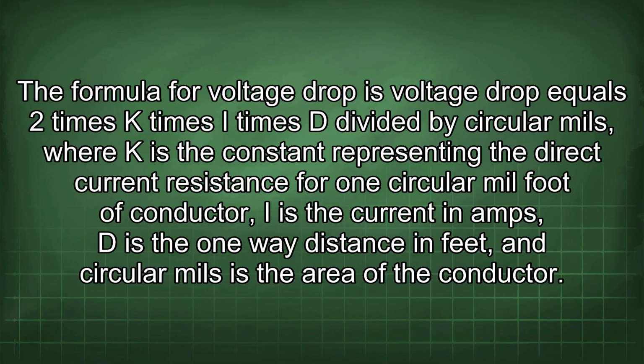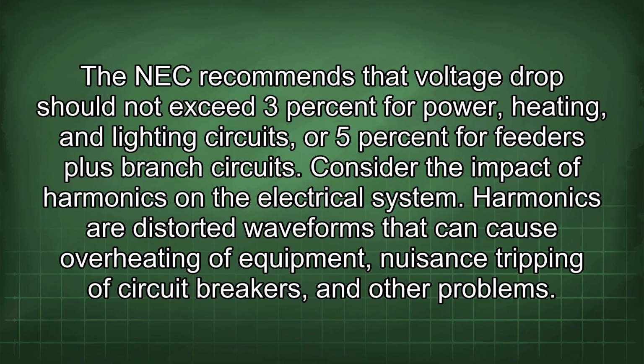The formula for voltage drop is voltage drop equals 2 times K times I times D divided by circular mils, where K is the constant representing the direct current resistance for 1 circular mil-foot of conductor, I is the current in amps, D is the one-way distance in feet, and circular mils is the area of the conductor. The NEC recommends that voltage drop should not exceed 3% for power, heating, and lighting circuits, or 5% for feeders plus branch circuits.